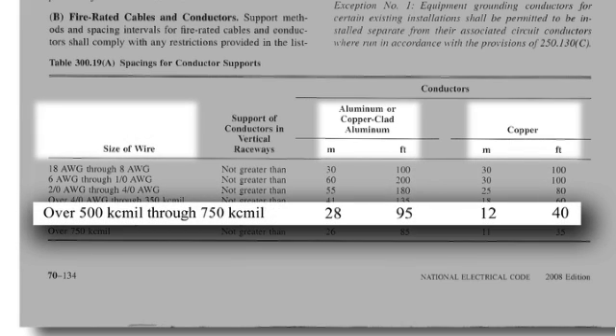For example, a 500 kcmil copper conductor installed in a vertical application must be supported every forty feet compared to ninety-five feet for an equivalent ampacity 750 kcmil aluminum alloy conductor. Because aluminum feeders are generally half the weight of the equivalent ampacity copper feeders, fewer supports are required when converting to aluminum alloy conductors.